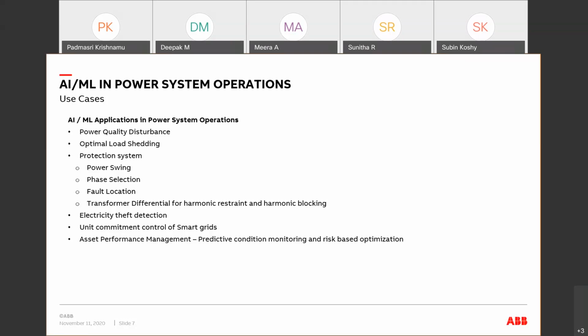The accuracy of the fault location is severely affected by the presence of varying fault resistance. There is a good amount of literature wherein ANN based models are used for fault location. This uses the rate of rise of the incremental current, which seems to be giving an accurate location of the fault. And a transformer differential. So this is also something which perhaps we can look at in a little bit more detail in the next few slides.